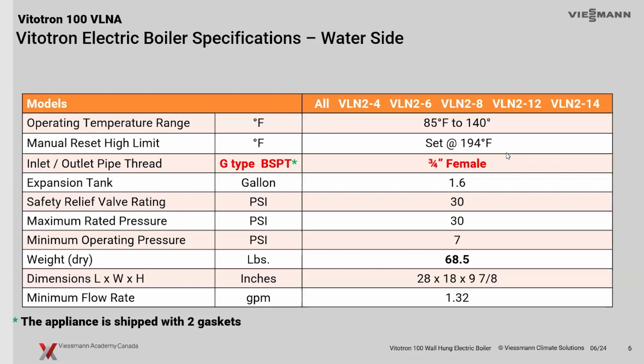It does have a manual reset limit. It's interesting how the limits are wired on these. They are a low voltage operation to essentially disable the elements. We'll show you how that works in a little bit. But at 194 Fahrenheit, we're going to trip that manual reset. It's just a little mechanical limit there you can push to reset.